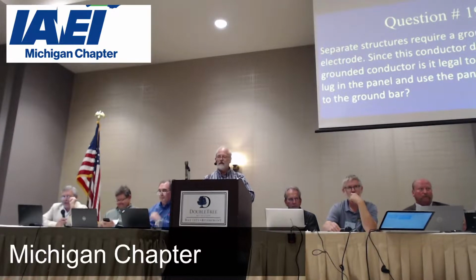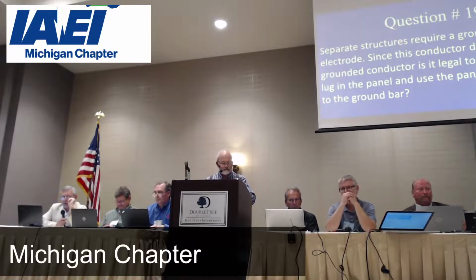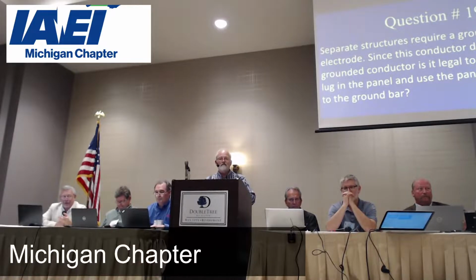So let me ask you another question though. Is the grounding electrode conductor part of your ground fault current path? It's not. I'll save you the answer. We don't consider that part of the ground fault current path. 250.4(A)(5) states very clearly that the earth shall not be used as a ground fault current path. So we're not talking about fault current going through the enclosure in this instance.